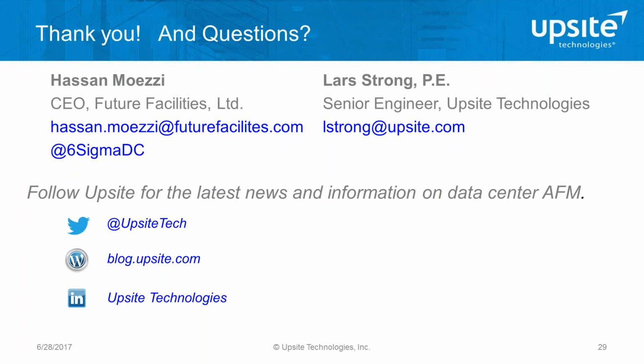I'll answer that from the virtual facility side—I'm not the technical expert, but we handle exactly these situations. For calibration, we instrument the room for temperature measurement over a period of time, and for airflow we take readings such as barometric readings under pressurized floor voids, then balance and calibrate the room accordingly. There will be variations, but we have ways of calibrating for that. It's absolutely necessary to calibrate before moving forward—we'd never recommend improvements to a room without first doing the modeling and calibration.